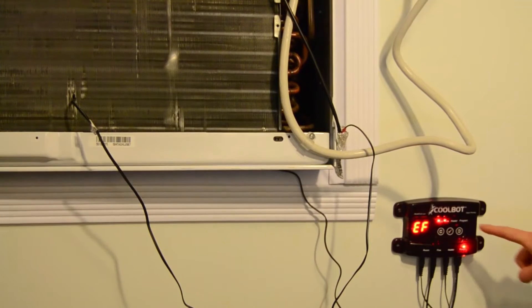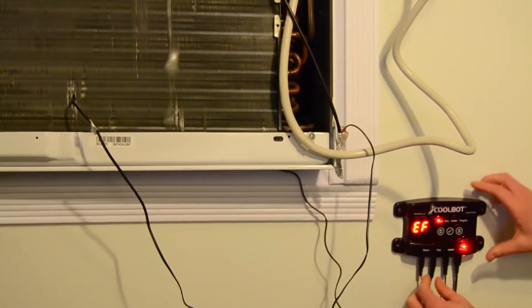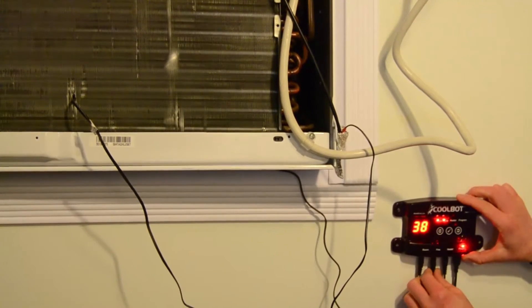An EF code and a blinking light over fin means that your fin wire is having an error. The first thing you want to try is to make sure that the wire is fully seated by unplugging and re-plugging the wire two to three times.